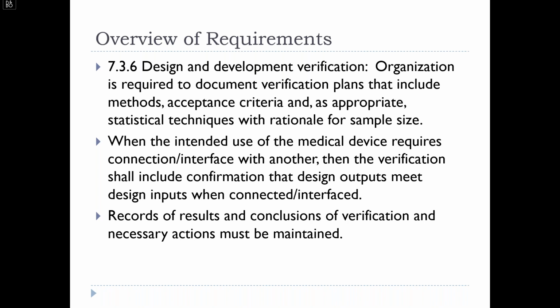When the medical device requires a connection or interface with another, so maybe it's part of a larger operating system, then the verification needs to include confirmation the design outputs are met when the device is in fact connected or interfaced and functioning as it would for an end user. The records of results and conclusions of verification and any necessary actions resulting from verification need to be maintained.